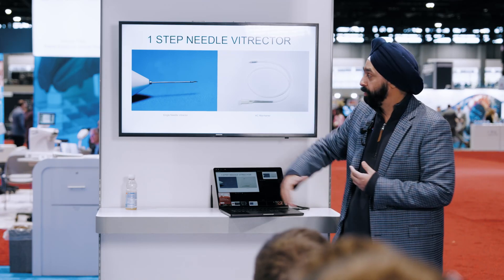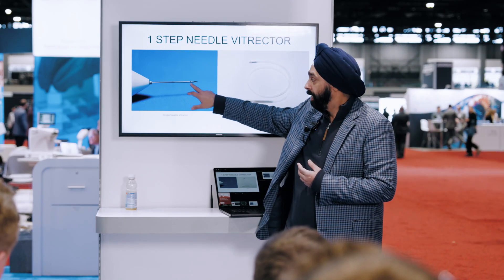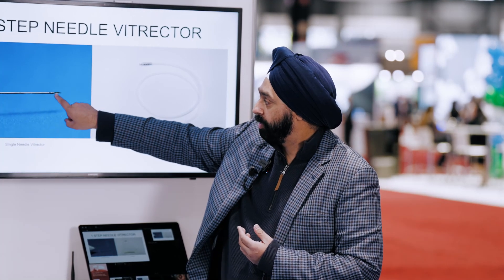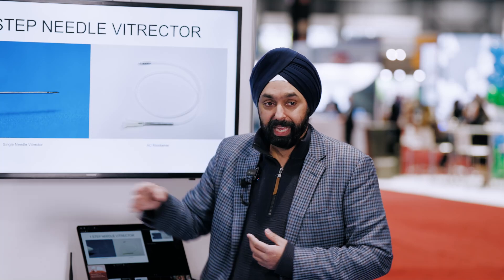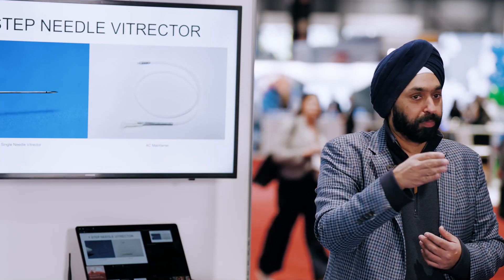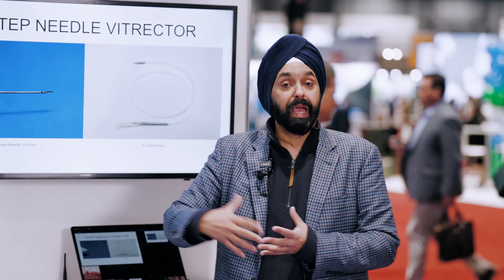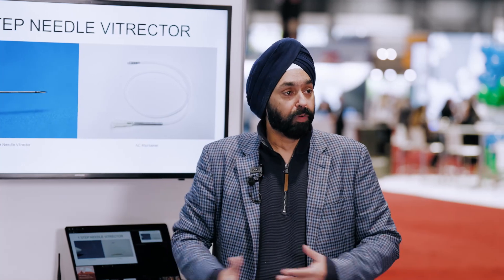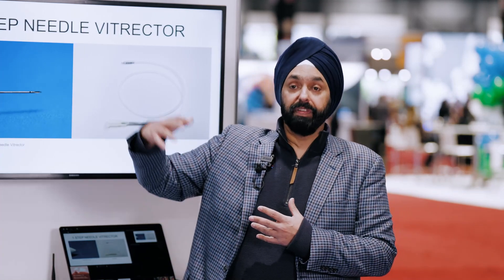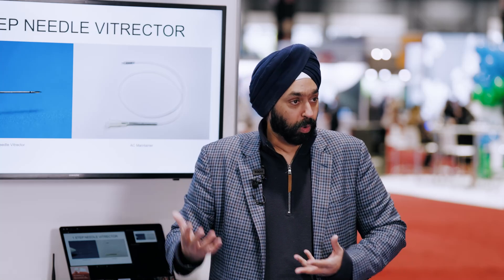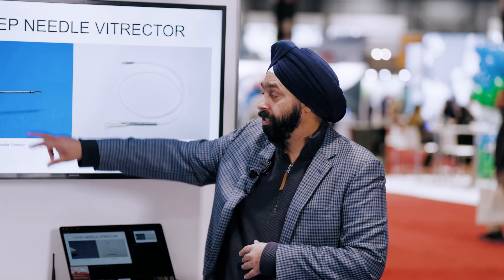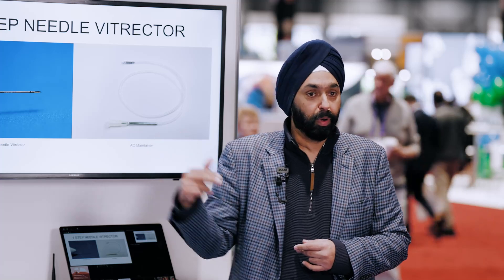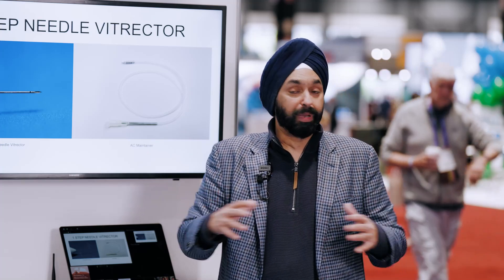The One Step is basically a 27-gauge needle with a port for aspiration or vacuum. Just behind the tip, there's a small opening with a dual-blade cutter that goes bi-directional. Depending on your phaco machine — a Centurion or Stellaris — it can run anywhere from 5,000 to 15,000 cuts per minute. It's attached to the phaco machine like a vitrector. Then you have an AC maintainer in the anterior chamber through just a 1.0 incision to keep the chamber formed. No trocars, no viscoelastic.